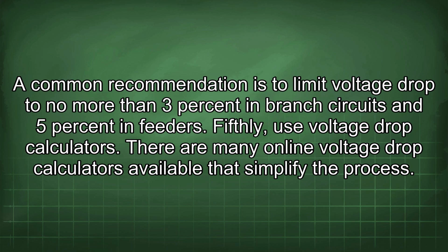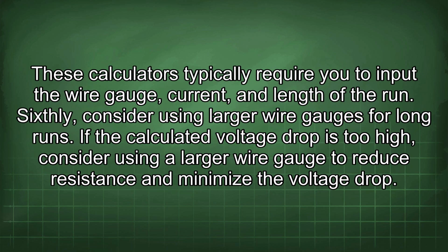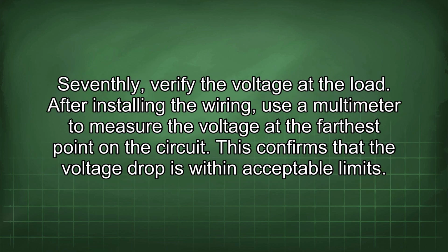Fifthly, use voltage drop calculators. There are many online voltage drop calculators available that simplify the process. These calculators typically require you to input the wire gauge, current, and length of the run. Sixthly, consider using larger wire gauges for long runs. If the calculated voltage drop is too high, consider using a larger wire gauge to reduce resistance and minimize the voltage drop.